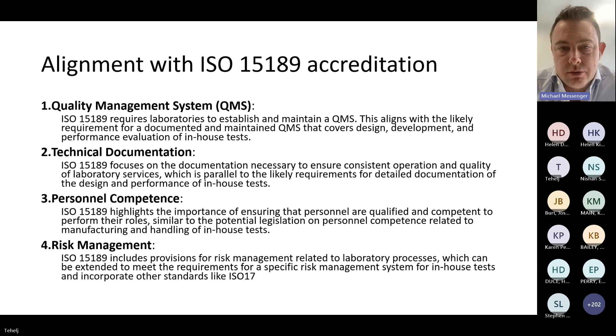ISO 15189 also focuses on documentation retention necessary to ensure consistent operation and quality of laboratory services. And this is parallel to the likely requirements for detailed documentation of the design and performance of in-house tests. Again, 15189 highlights the importance of ensuring that personnel are qualified and competent to perform their roles. And this is similar to the potential future legislative requirements on personnel competence related to manufacturing and handling of in-house tests. And finally, ISO 15189 includes provisions for risk management related to laboratory processes, which can be extended to meet the requirements for a specific risk management system for in-house tests and incorporate other standards like ISO 14971, which is the medical device risk management standard. So there's a lot already within what you do in terms of your best practice around 15189, which will help you on your journey to compliance with the future regs.